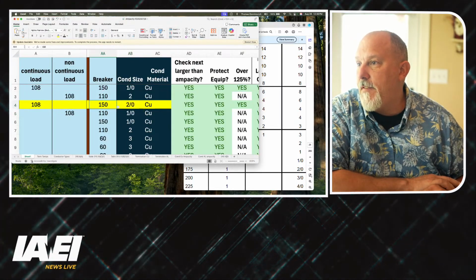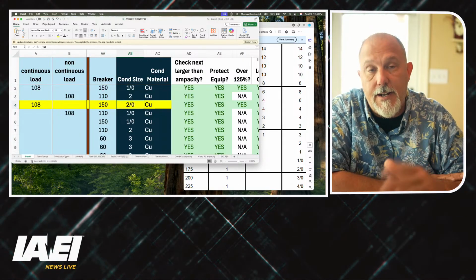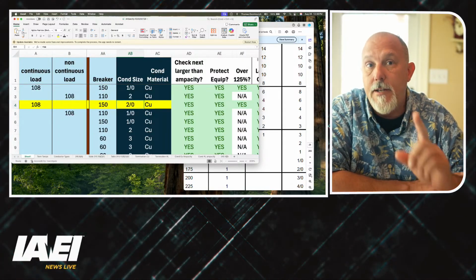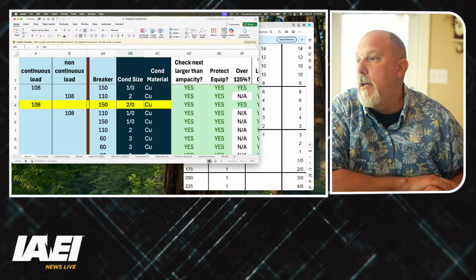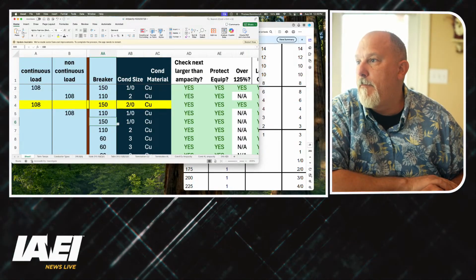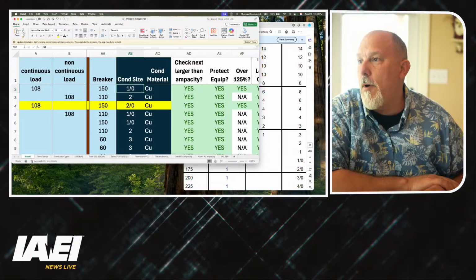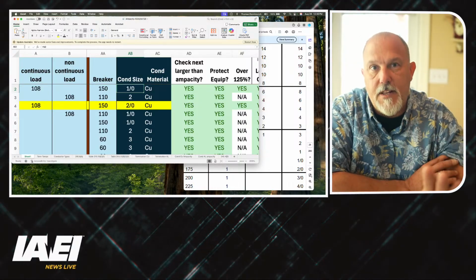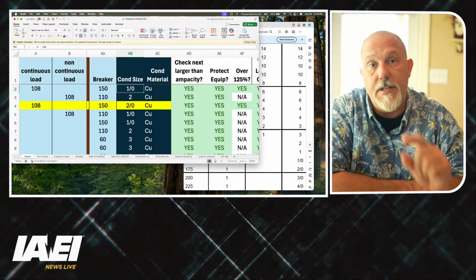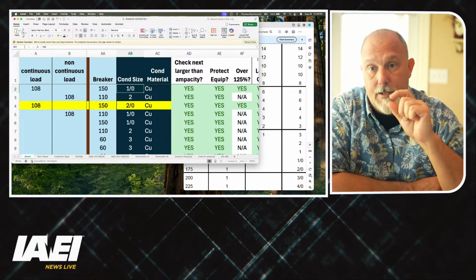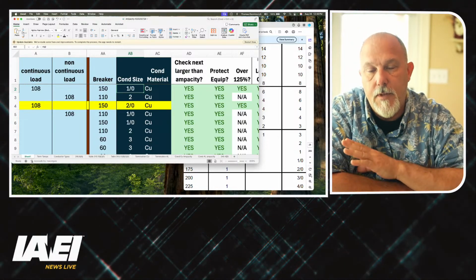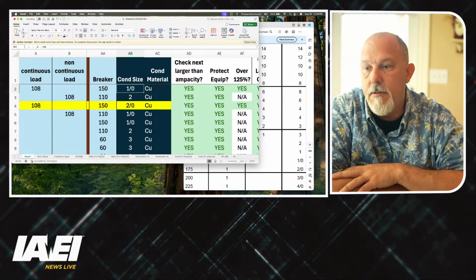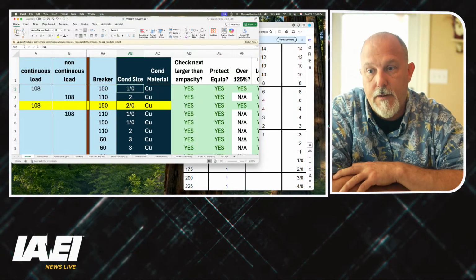So there is 150 amp with a 2/0. That's perfectly fine. I can go larger than a 1/0. It wicks off more heat. There's 150 amp with a 1/0 conductor, and that's perfectly fine because a 1/0 copper conductor is the smallest conductor that I can put on that breaker.